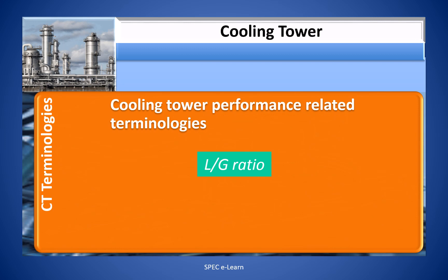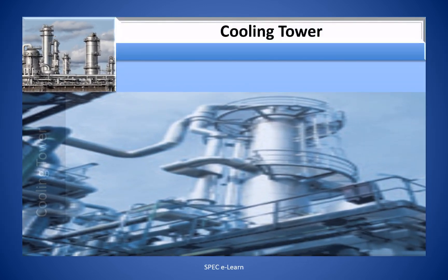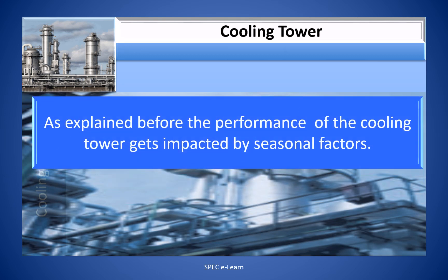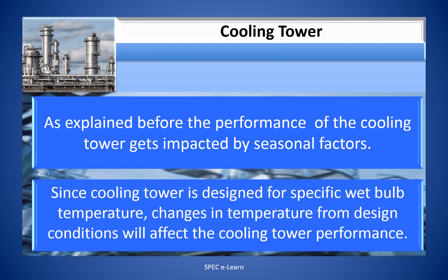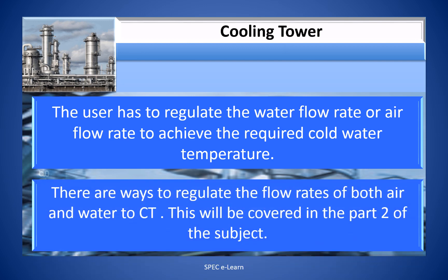L/G ratio is the ratio of the mass of water flow to the mass of air flow to the cooling tower. The performance of the cooling tower is impacted by seasonal factors. Since the cooling tower is designed for a specific wet bulb temperature, changes in temperature from design conditions will affect performance. The user must regulate the water flow rate or air flow rate to achieve the required cold water temperature. Ways to regulate these flow rates will be covered in Part 2.